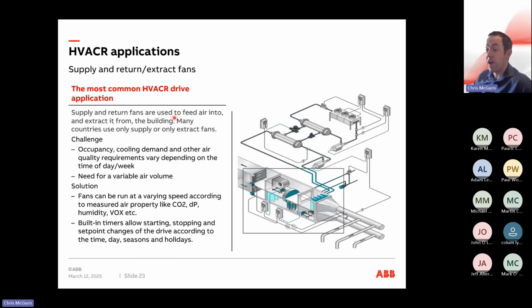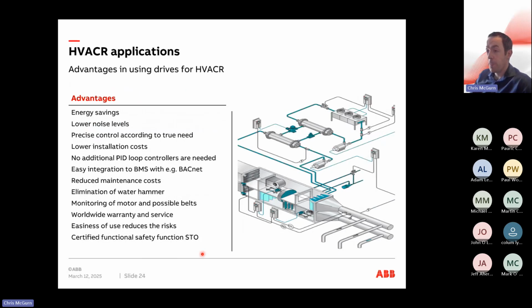Again, supply and return extract fans. The requirement of these is to match the cooling demand in the room at different times and days of the week. So they need to be programmed in a way that they can turn on when people are actually in the building or whenever it's actually required. And VSDs can be used to vary that speed at those specific times and run on specific timers so that they can switch on only when they're actually needed and turn off at night time or during holidays and that type of thing. So it gives you just another level of control, so you're not wasting energy when it's not needed.